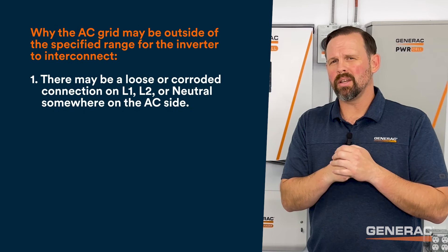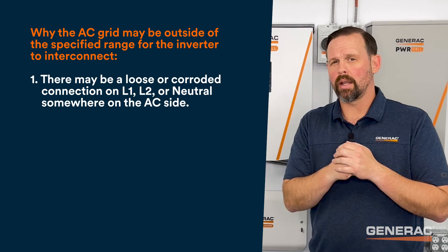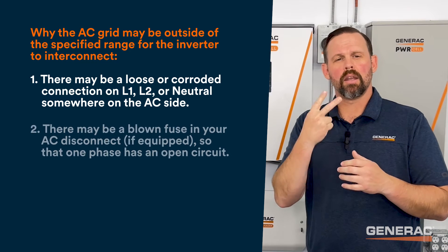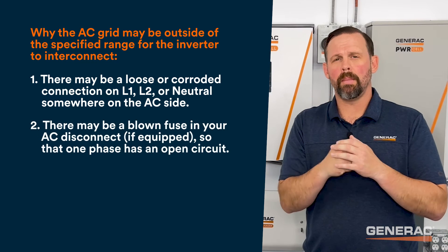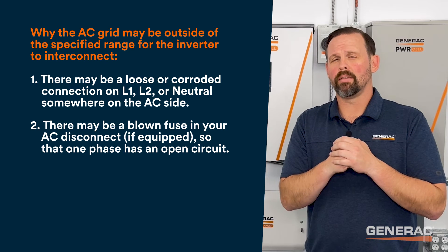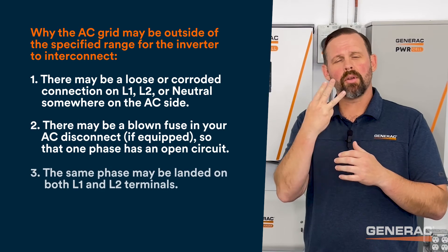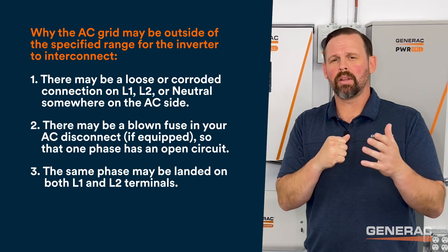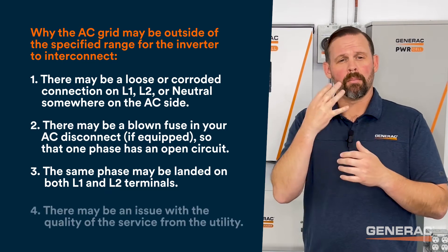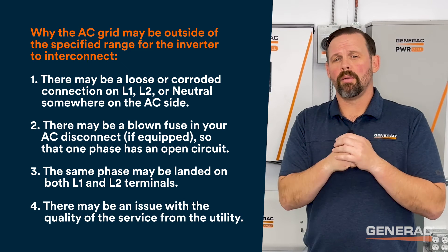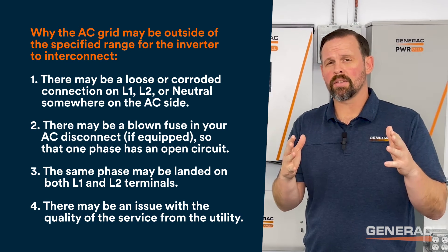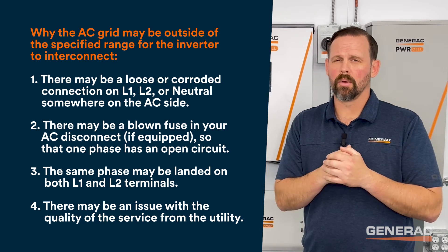Number one, there may be a loose or corroded connection on line 1, line 2, or neutral somewhere on the AC side. Number two, there may be a blown fuse in your AC disconnect if equipped, so that one phase has an open circuit. Number three, the same phase may be landed on both line 1 and line 2 terminals at the inverter. Number four, there may be an issue with the quality of service from the utility. In all cases, the first place to start is with your multimeter.